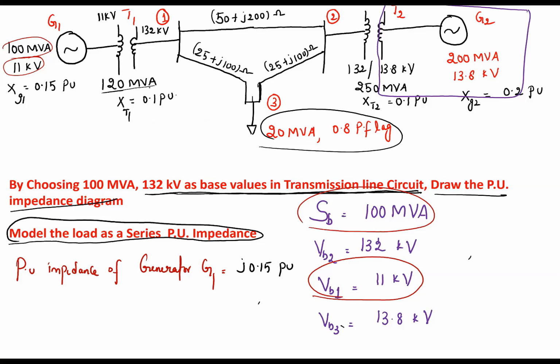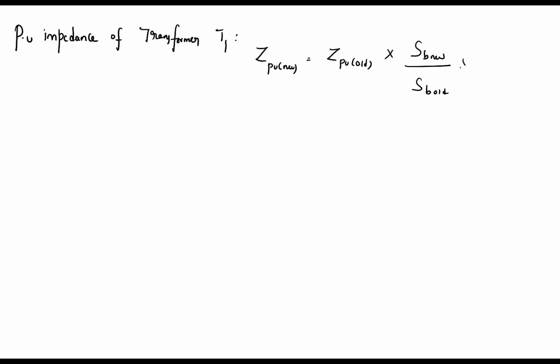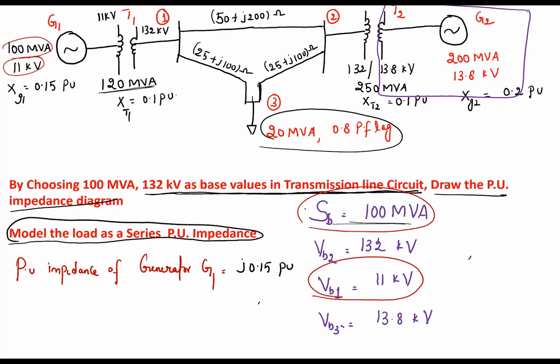But what is the machine rating? Machine rating is 120 MVA, but our base value is 100 MVA. So here there is a mismatch. So again we have to calculate the per unit impedance of the transformer. So the per unit impedance of transformer T1 is given by, we have to use the formula: Z per unit new equals Z per unit old into new base MVA by old base MVA into old base voltage by new base voltage, whole square. Okay, so now the old base MVA is 120. Here the base voltage on the low voltage side is 11 kV, and on the high voltage side is 132 kV. So base voltages and machine voltages are matching.